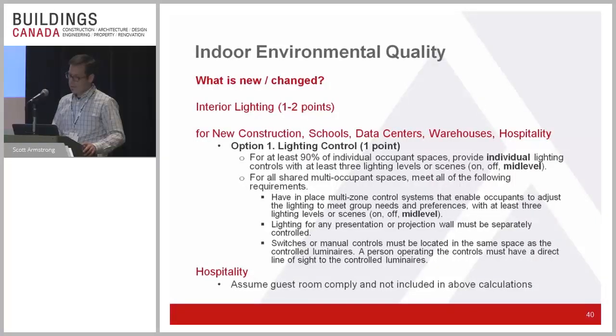Lighting controls have changed a little: 90% of individual occupants have individual lighting control for three levels. Three levels doesn't mean 20%, 50%, 75%—it means on, off, or 50%, mid-level as they say. Mid-level can be anywhere from 30 to 70% of total lighting value. It's not a huge requirement, but it's a little more controllability than on or off. Before, controllability of lighting could only be on or off—now it's on, off, and somewhere in between, because if you've ever turned on the bathroom light in the middle of the night, you realize mid-level is pretty nice sometimes.